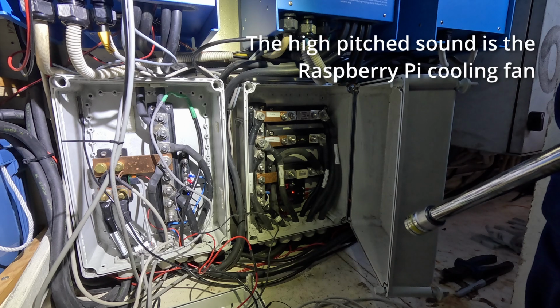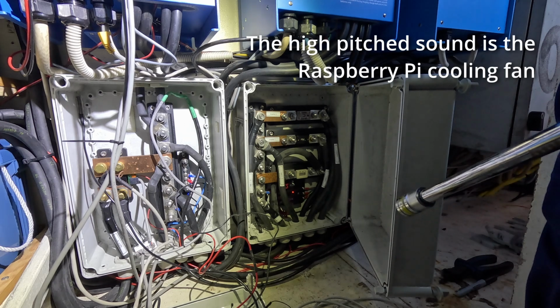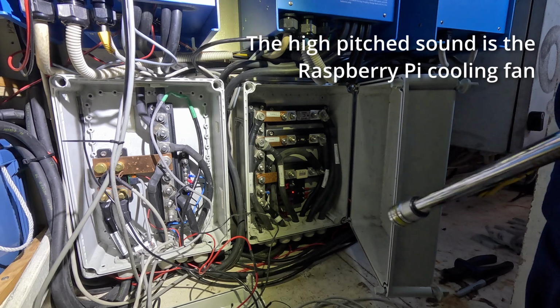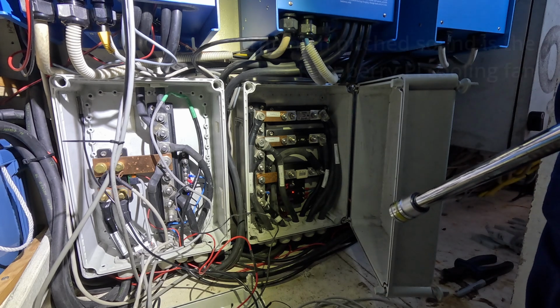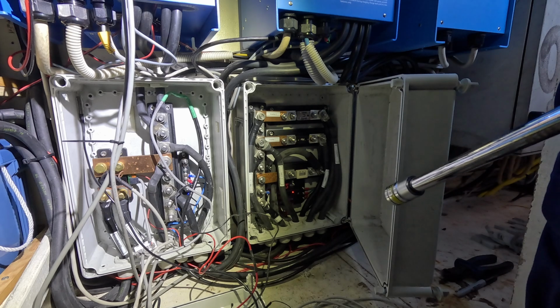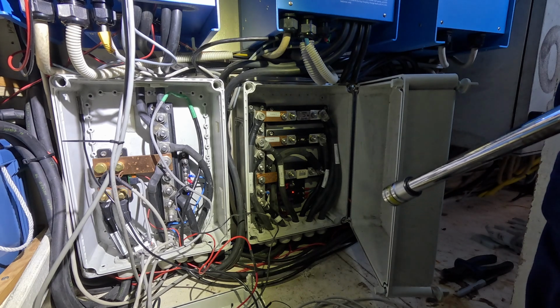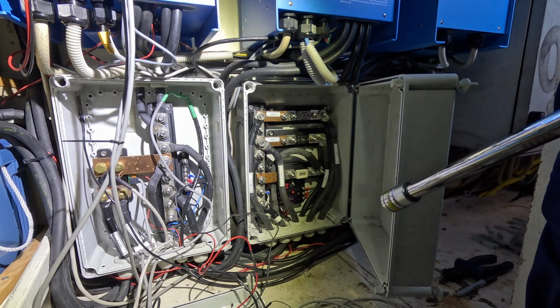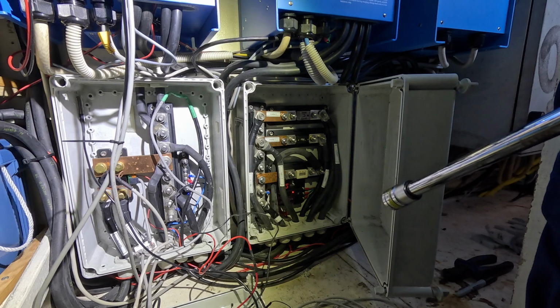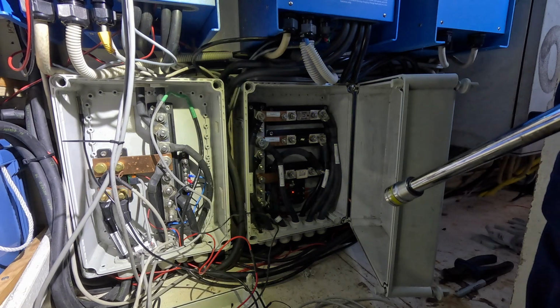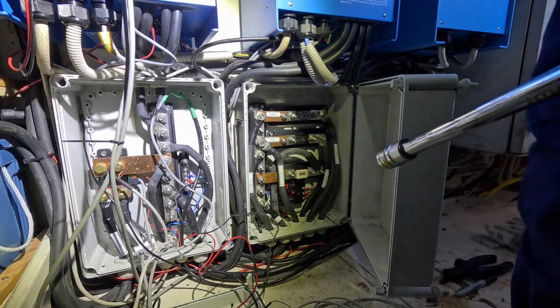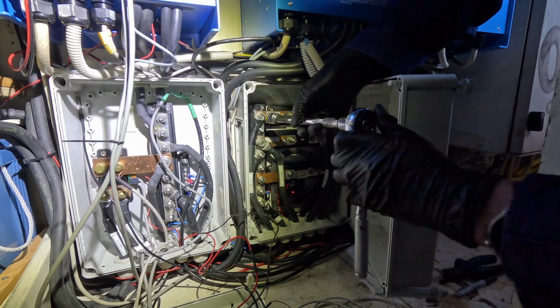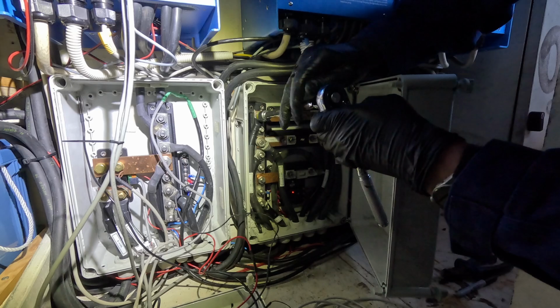While I'm having this box open, I will also check that all the connections are nice and tight. Loose nuts, loose bolts, making poor connections is the main source of heat and possibly fire. So I'll use this opportunity to check that all bolts, all nuts are securely fastened.